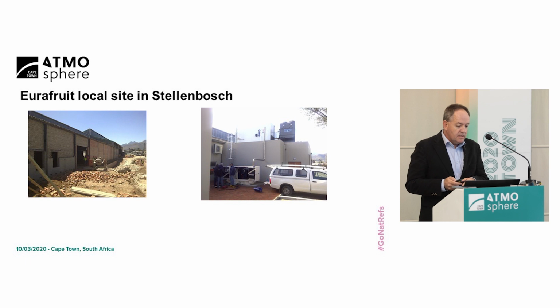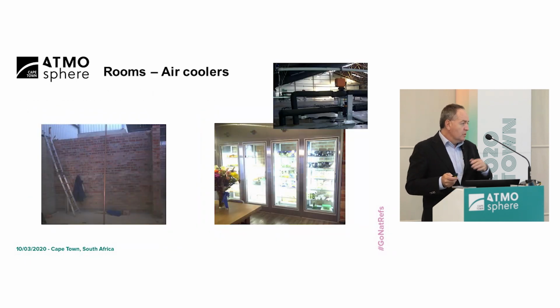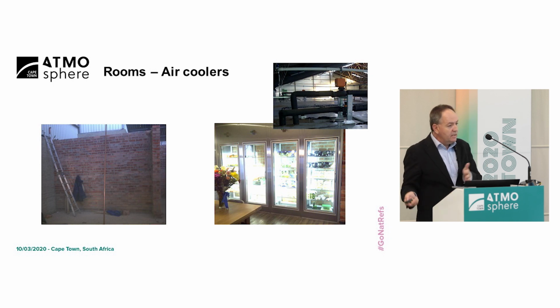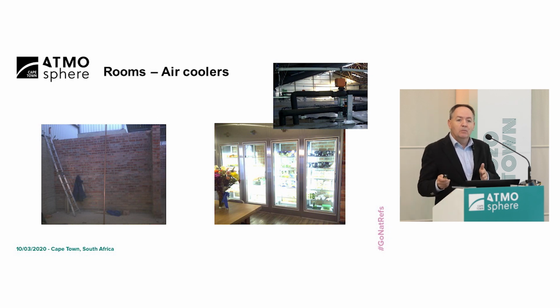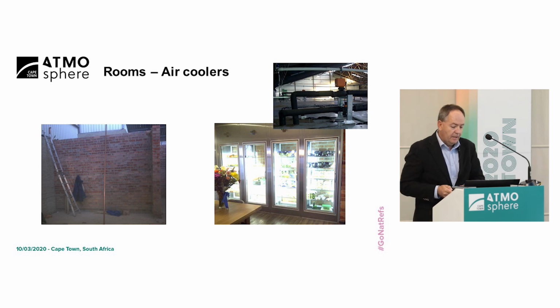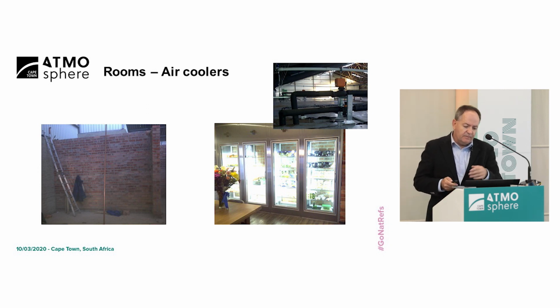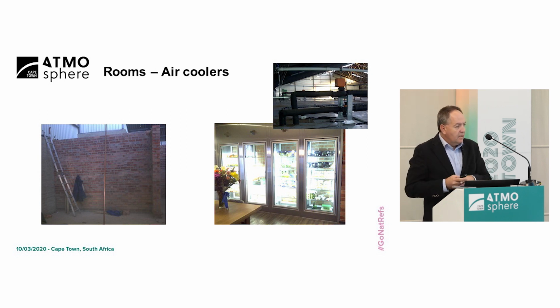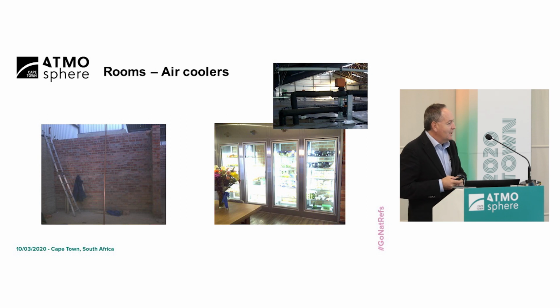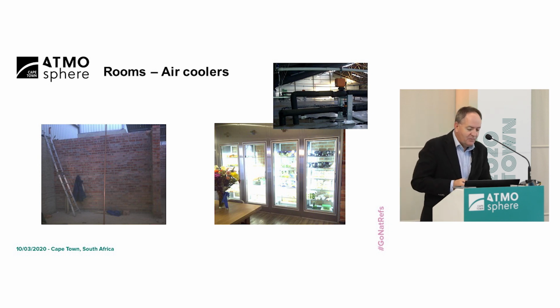So it's an ammonia system, but of course in this case the ammonia is contained in the plant room. So it's a secondary cooling system. We're not circulating ammonia into the pack house, which made it significantly safer. One peculiar thing the client wanted, he wanted to simulate the glass door fridges that his clients have, that Woolworths has, and then he would label the produce that he sends off and date it, and if he's got a complaint from Woolworths, then he can go check his sample in his fridge.